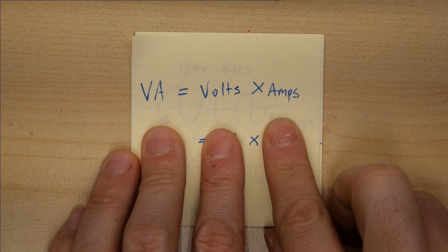So as I'd mentioned, VA stands for volts times amps. If you have a device that uses 1 amp of current and it's running on 120 volts, then the number of VA it's consuming is exactly 120 times 1, or 120 VA. And remember, the transformer right here is 300 VA. It can handle something around 2.5 amps at 120 volts, and that should fit within the rating of this transformer.